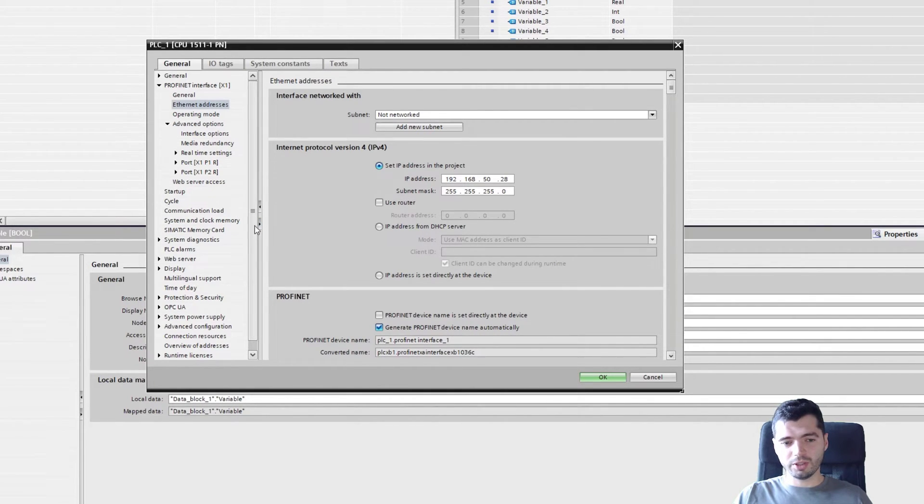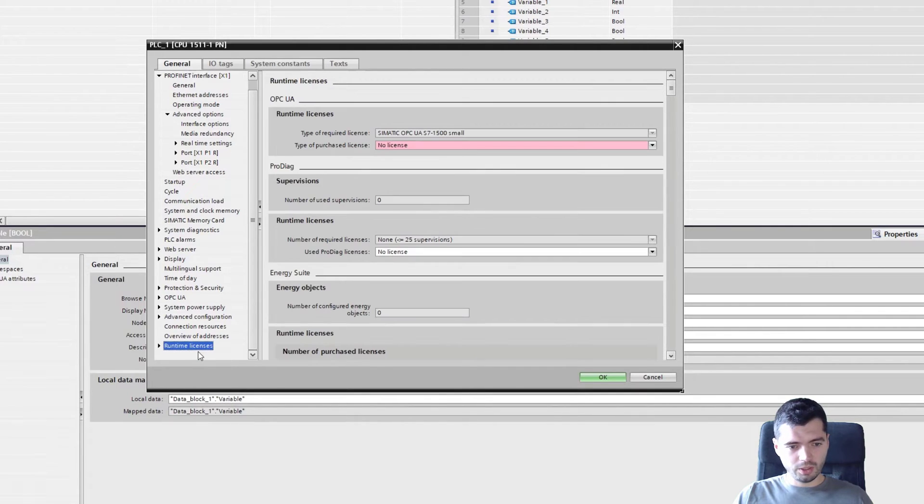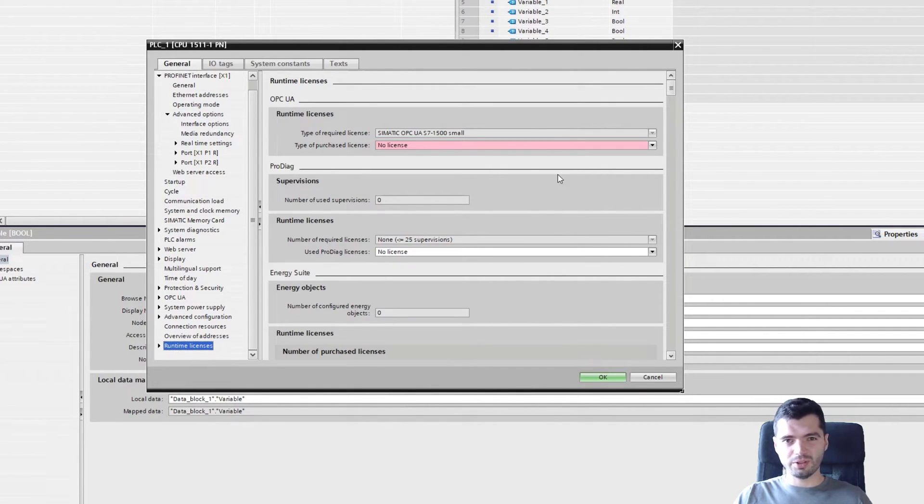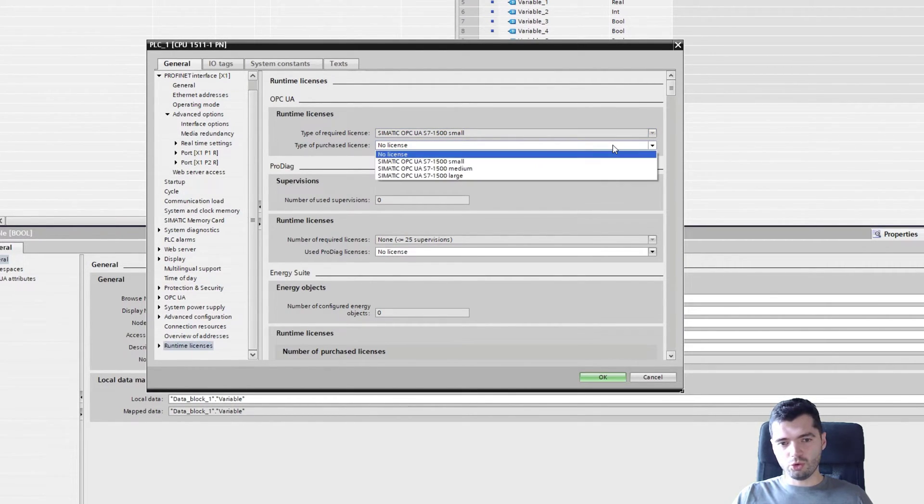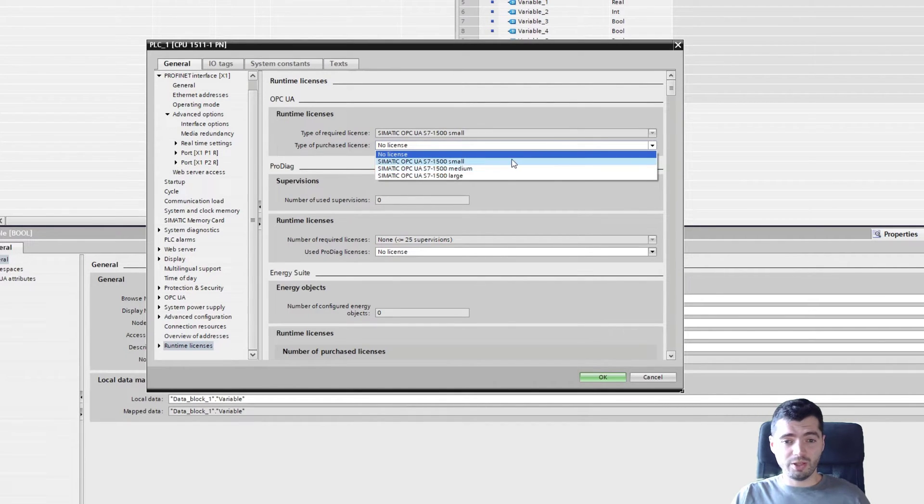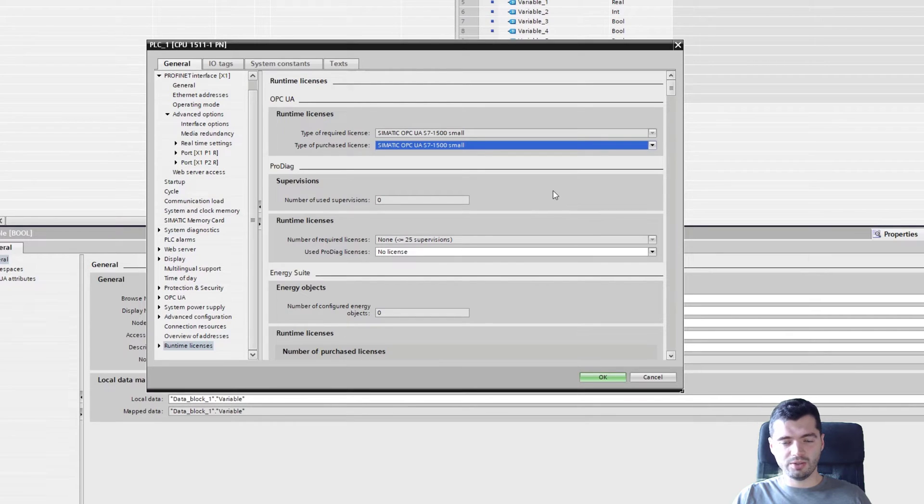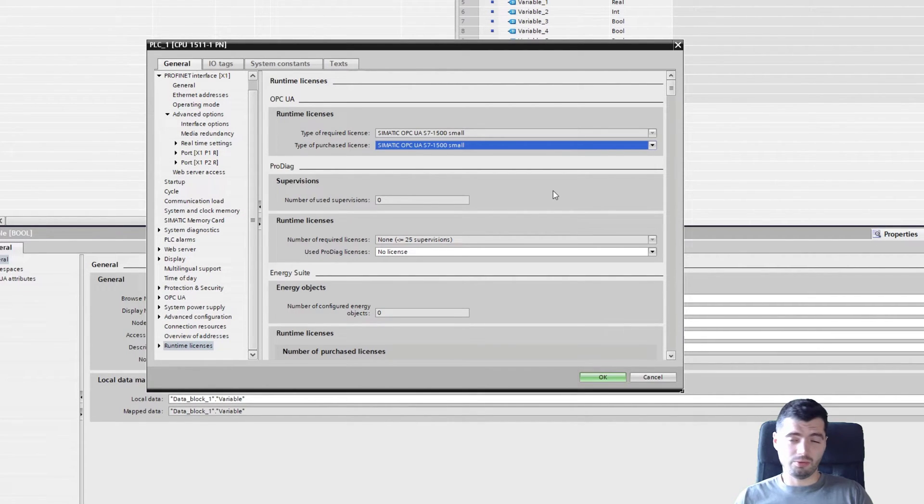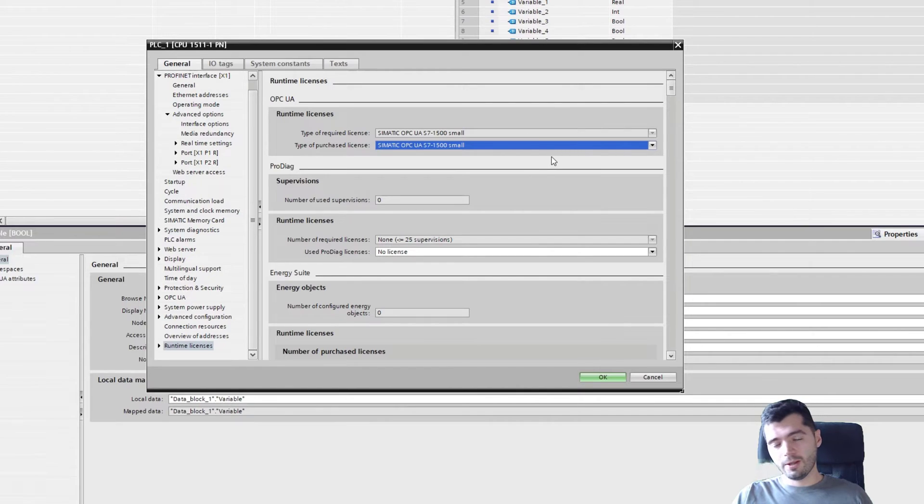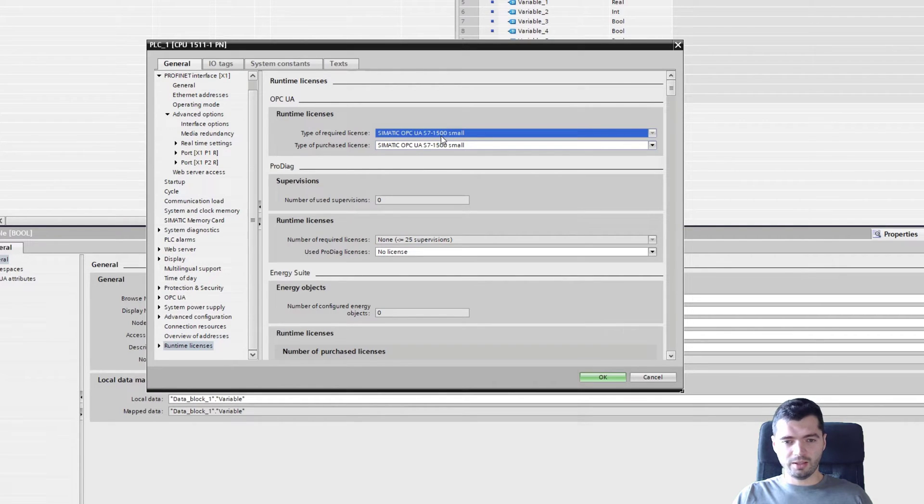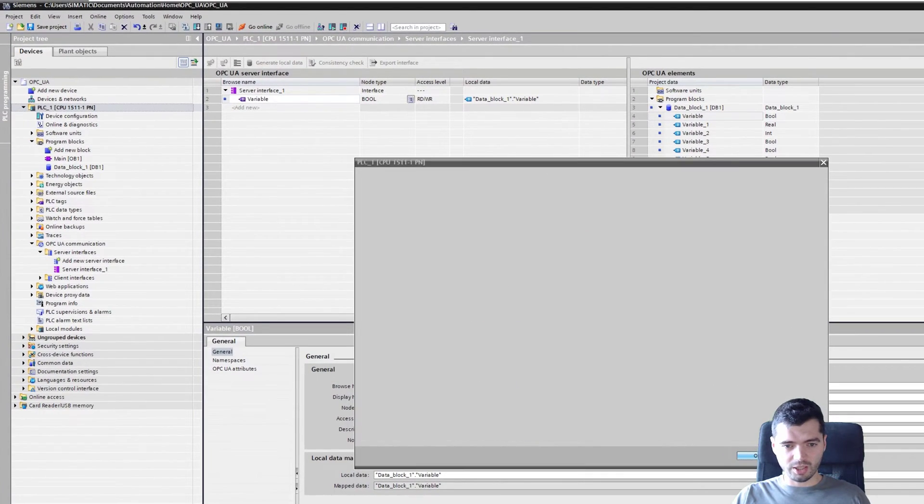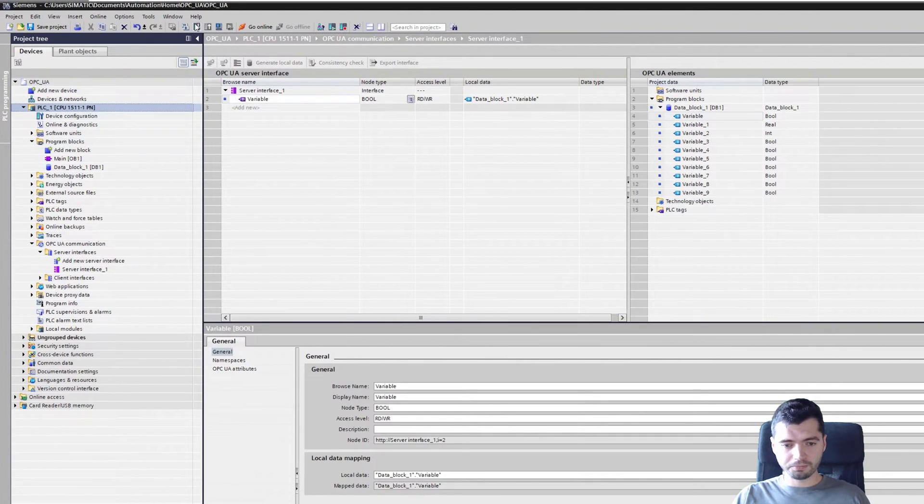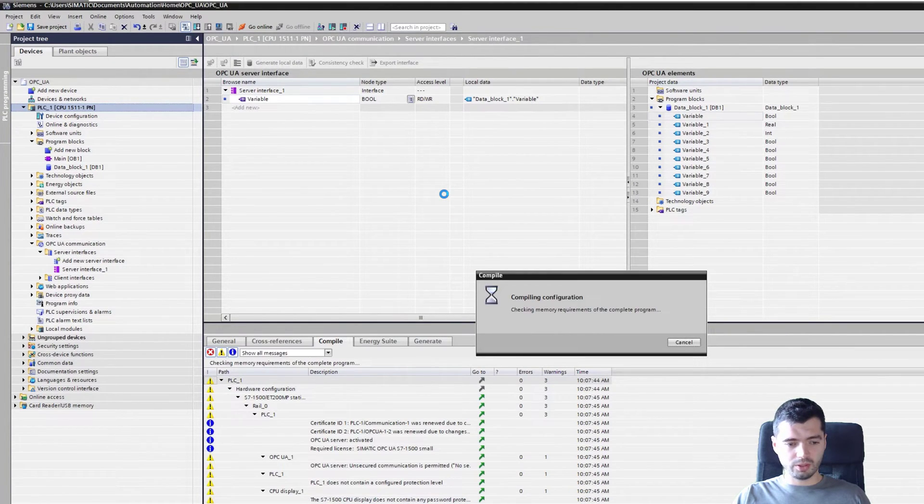But if you go now to download it, it will throw you an error saying you don't have a license. Because OPC UA on the S7-1500 is a licensed option. And based on the size of your PLC, you should select the correct license size. So I defined my PLC to be a 1511, which means I need an OPC UA 1500 small license. This is something that you buy as a paper license. Just contact your distributor, get yourself a paper license for the size of your PLC. And then here you need to say OK, yes, this is the license that I have. Long story short, if you select anything that is of the right size or bigger, it's fine. If you have, let's say, a medium PLC and select a small license, then obviously it's not fine.